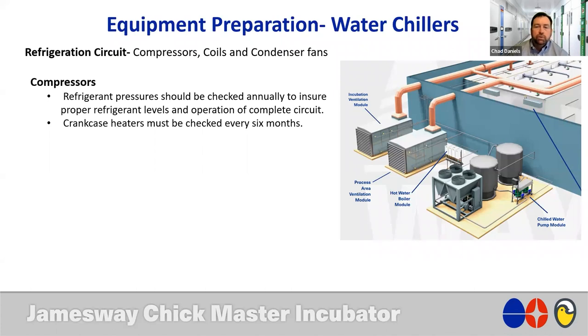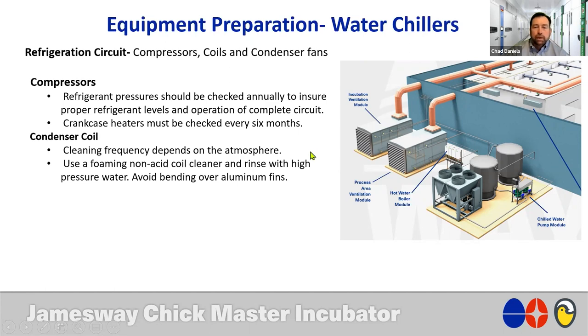Also with chillers that work for HVAC systems, they'll have a crankcase heater on them. It's important to make sure that those are drawing the right amperage and that those are working. You don't want your chiller to cold start without crankcase heaters. Again, condenser coil, it's important that they're clean, but again, because it's a chiller at ground level, it's easier for debris such as leaves and trash and things of that nature to get drawn into them.